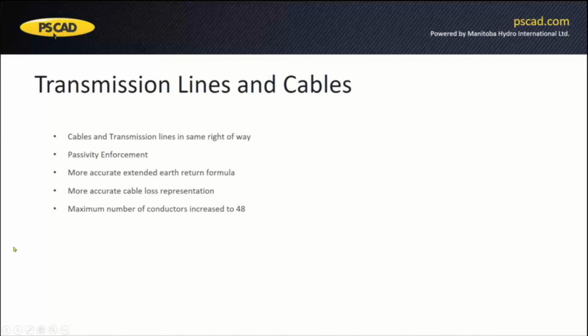And there's a more accurate extended earth return formula introduced. This will improve the stability in aerial cables. It is especially important for GIS studies with short lines.